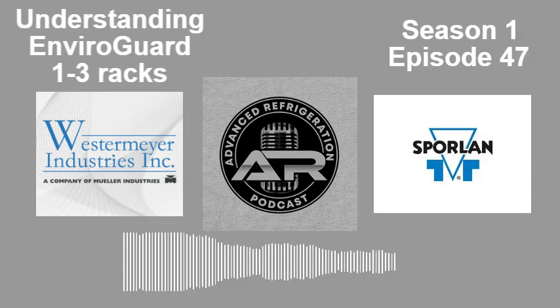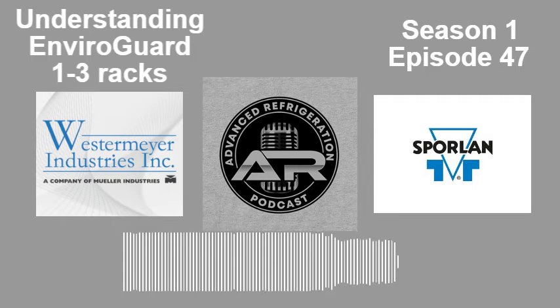Now, it gets different with this because you also have to remember an Enviro-Guard condenser is not 3/8 tubing. Typically, it's 1/2 inch. So your condenser is technically like your receiver. So most Enviro-Guard condensers were massive, with 1/2 inch tubes instead of 3/8 tubes. We had this happen to us: somebody quoted a condenser change out and didn't realize that it had 1/2 inch tubes and it was an Enviro-Guard and it was sized a lot differently. You really need to talk to the condenser manufacturer about that before you just go throwing one on all willy-nilly. And whatever you do, do not throw a microchannel on it, because you're not going to get any subcooling.